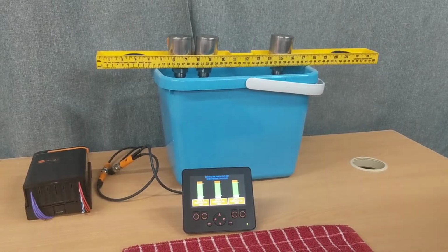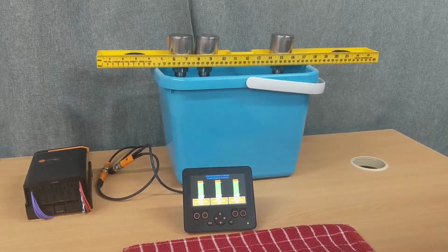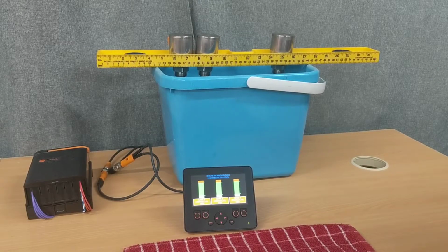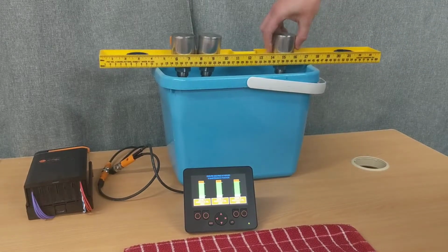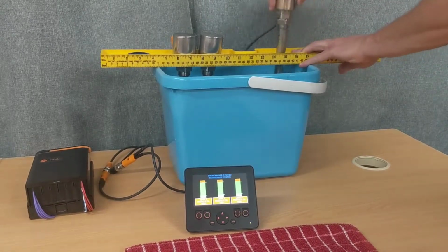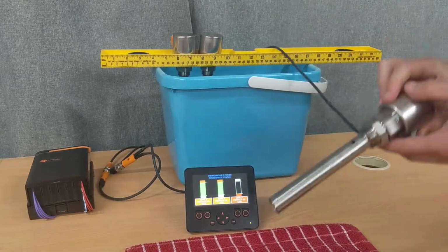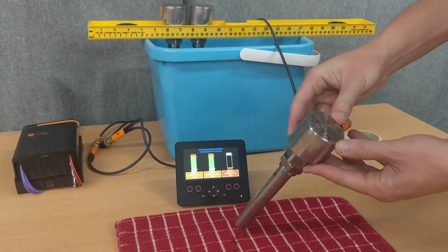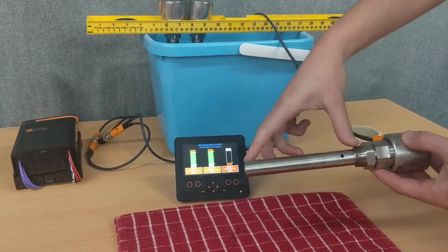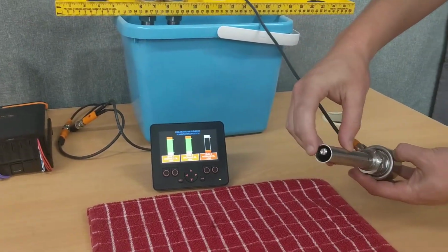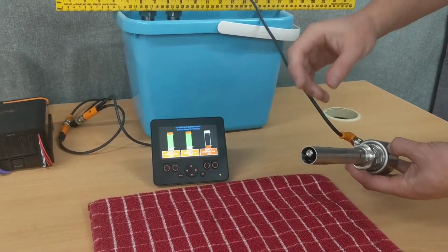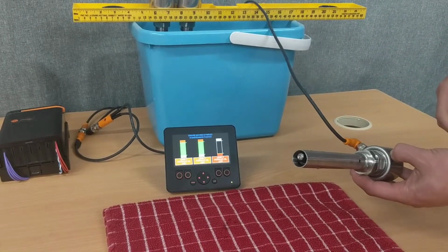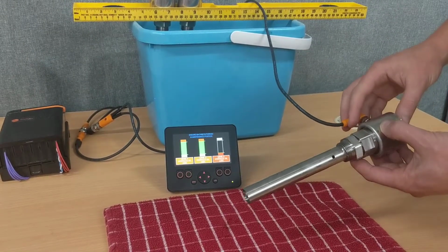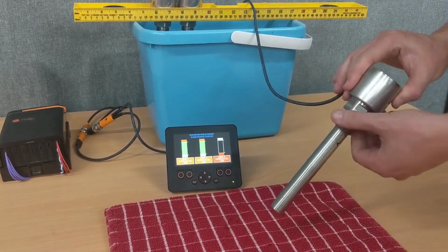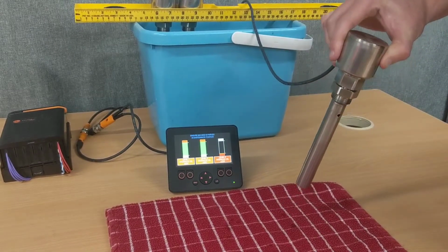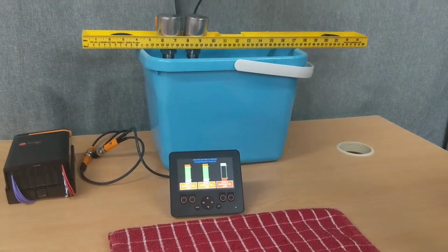This is a video display of a multi-level display system based around the IFM guided wave radar sensor. This sensor here uses the LR9020 sensor and the coaxial tube and probe inside. Sensors available from 100mm to 1600mm. It requires 18 to 30 volts, so don't get caught with a 12 volt vehicle application.